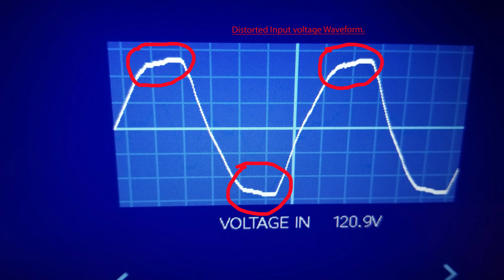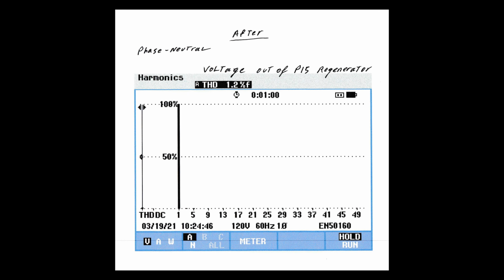Now let's put a regenerator system in line and see what happens. Here we have our after harmonic chart, and it's showing the power coming out of the P15 regenerator has a total harmonic distortion of 1.2% compared to the 6.9% we had on the power going into the regenerator from our house outlet. So it's a 5.7% reduction in total harmonic noise. And as you can see, past the first order fundamental of your 60 hertz, we have no measurable third, fifth, sixth, seventh, and above harmonic distortion. So the regenerator has cleaned up the 60 hertz of the utility power quite a bit, giving us a nice clean, fairly undistorted signal going out to our electronic equipment.